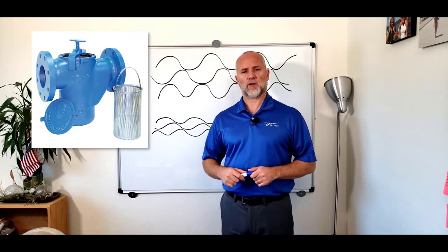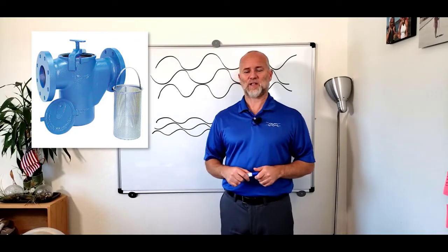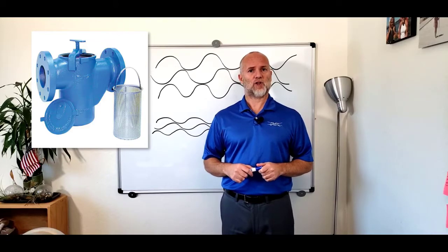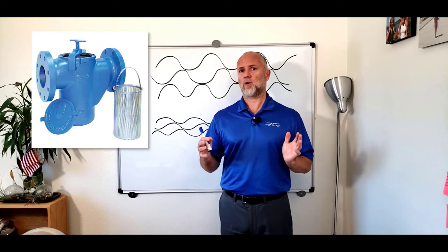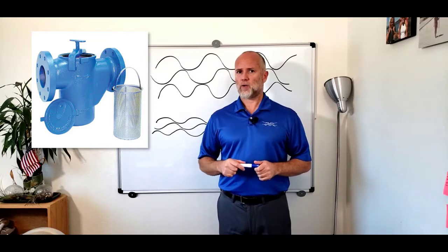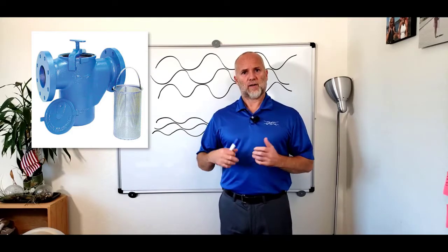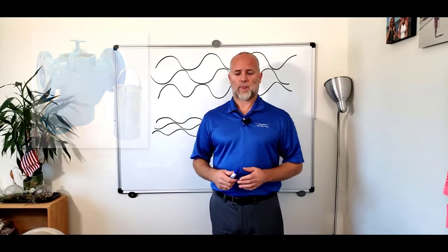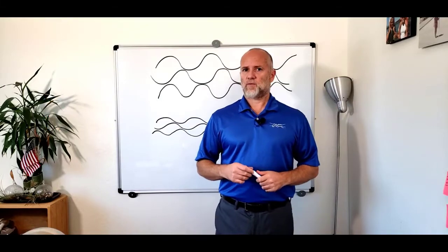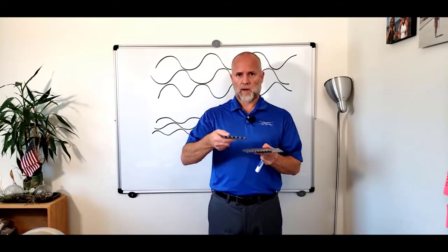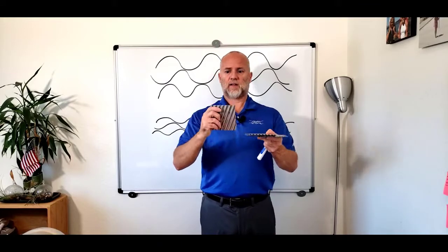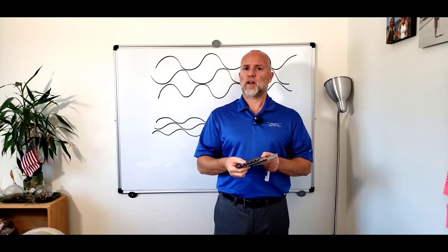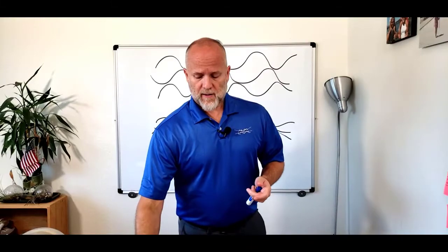The main challenge that we see, speaking about plate and frame heat exchangers and strainers, is that in order to design the right mesh, you need to know the size of the channels inside of your heat exchanger. And that leads us to the concept of the pressing depth. We talked about the pressing depth in previous videos, but let's recap. Here you can see three examples of different pressing depths, and you can see that the size of the channel, of course, is different. Why is that important?